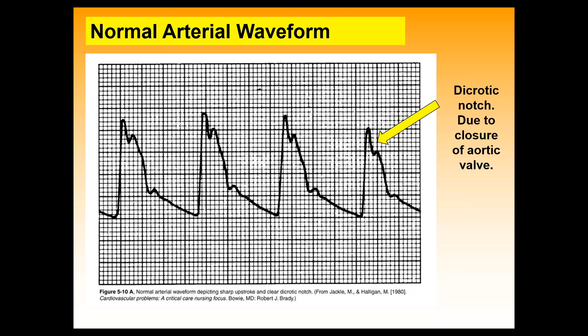And if you were doing this on the right side, the waveforms are very, very similar on the right side of the heart, leaving the right ventricle, because when the pulmonary valve shuts, you also get a notch. It's just that the pressure magnitudes are typically less on the right side, but the morphology is very similar. So you want a nice distinct dicrotic notch, a very distinct rising edge, a nice clean crisp waveform. If you see that, that's almost all you generally need to know, that you've got a relatively well optimized system. It's called critically damped, engineering-wise.